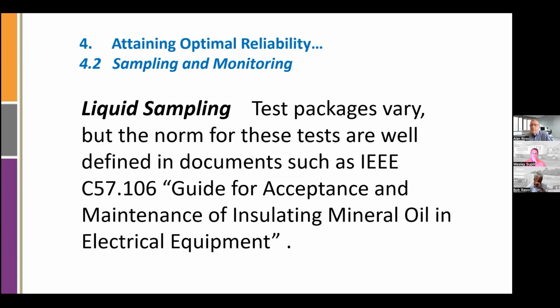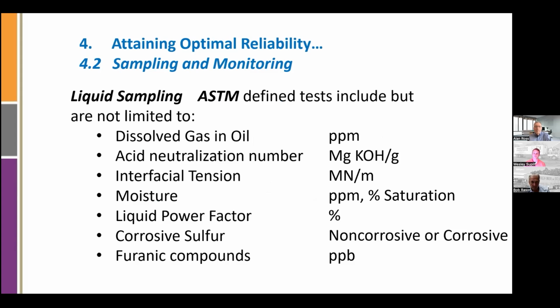Liquid sampling. Currently, it's IEEE C57.106. There's a guide similarly for esters, for silicone, for high molecular weight hydrocarbons. Those documents give guidance on where transformers should be for in-service. These are some of the tests. Probably familiar with these. DGA, a great test for looking at aging of insulation. There are key gases that go along with it, and also some different ways of looking at the data, such as the triangles that are popular. Moisture's a big deal to keep looking after. Liquid power factor, also tied to insulation degradation.